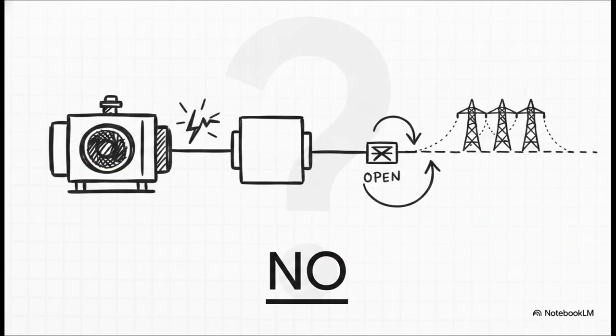Okay, let's dive right into this with a quick scenario. Imagine a fault occurs right at that generator-transformer interface. Your relay does its job and successfully commands the grid side breaker to open. Is the fault actually cleared? The answer is a massive, resounding no. It's really easy to think in terms of static grid isolation, but we have to remember a rotating machine is still involved here. The generator is going to continue supplying fault current through its own excitation system. Full fault clearance requires a whole lot more than just a single breaker clicking open.